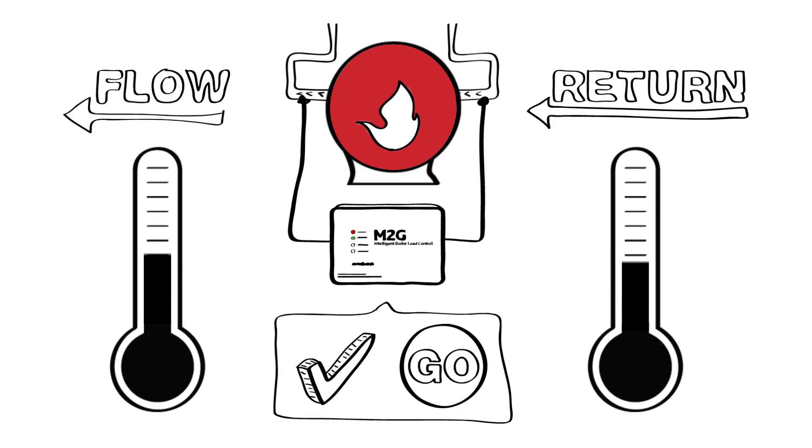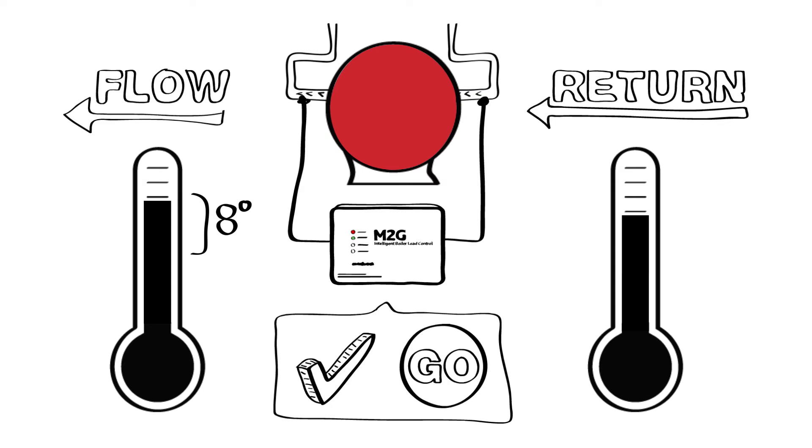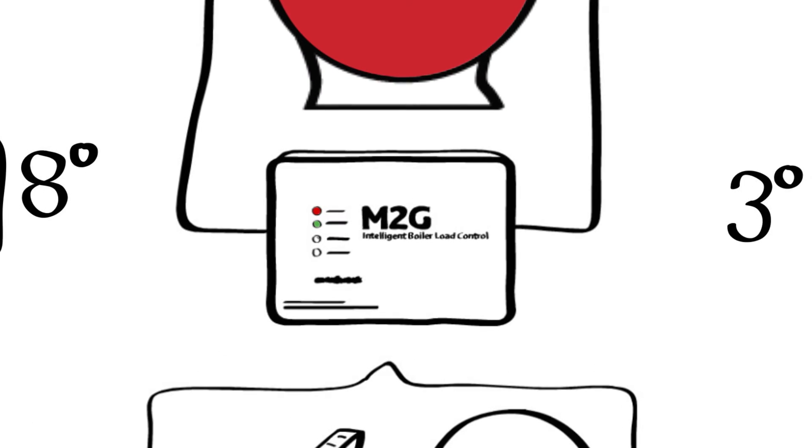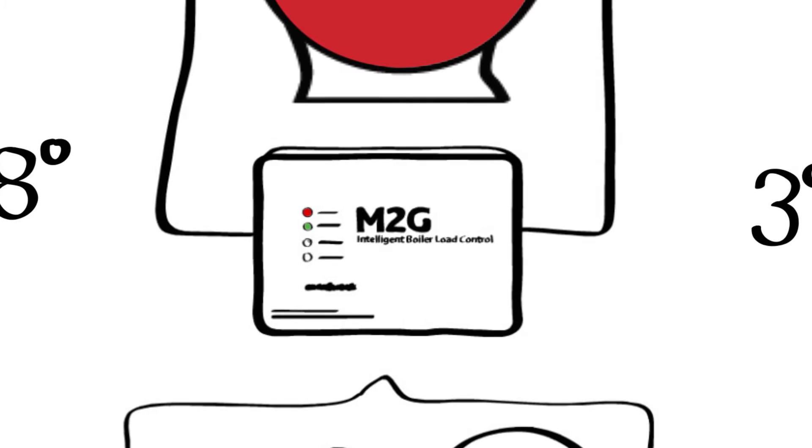As the boiler reaches its required temperature, M2G takes a snapshot reading of the flow and return. From these readings, M2G applies an 8 degrees dead band on the flow and a 3 degrees dead band on the return. Once the building has reached the desired temperature and the initial snapshot of the flow and return has been taken, the M2G then takes these readings every second and analyzes this data every 10 seconds.